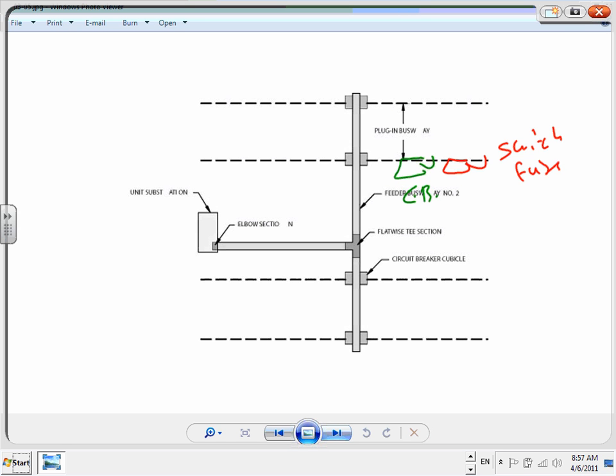If it's a switch and a fuse, I just want to remind you guys, you use 30 amp disconnects, and you go to 60 amps and 100 amps. These are the disconnect sizes, and you have the disconnect sizes right in here, page 312, if you're using fuses. So make sure you follow the 30 amp, 60 amp, 100 amp, and then inside them you can put different fuses. Up to 30 amp fuses I can put in a 30 amp disconnect switch. Or you can use circuit breakers.